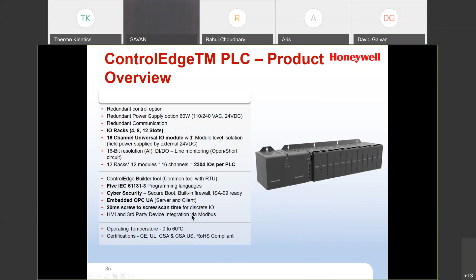We have customers right now who, because of the integration to Experion, bring in devices and let this ControlEdge PLC be the gateway, that divine gateway that eliminates a lot of the kludgy software connections that we're currently using today. We can use a physical hardware peer-to-peer gateway into Experion. It has 20 milliseconds of execution time. The C300 runs at 50. This one's at 20 milliseconds, so it's fast acting for discrete I/O control. And then we also have HMI third-party device integration via all the Modbuses that I spoke about earlier.